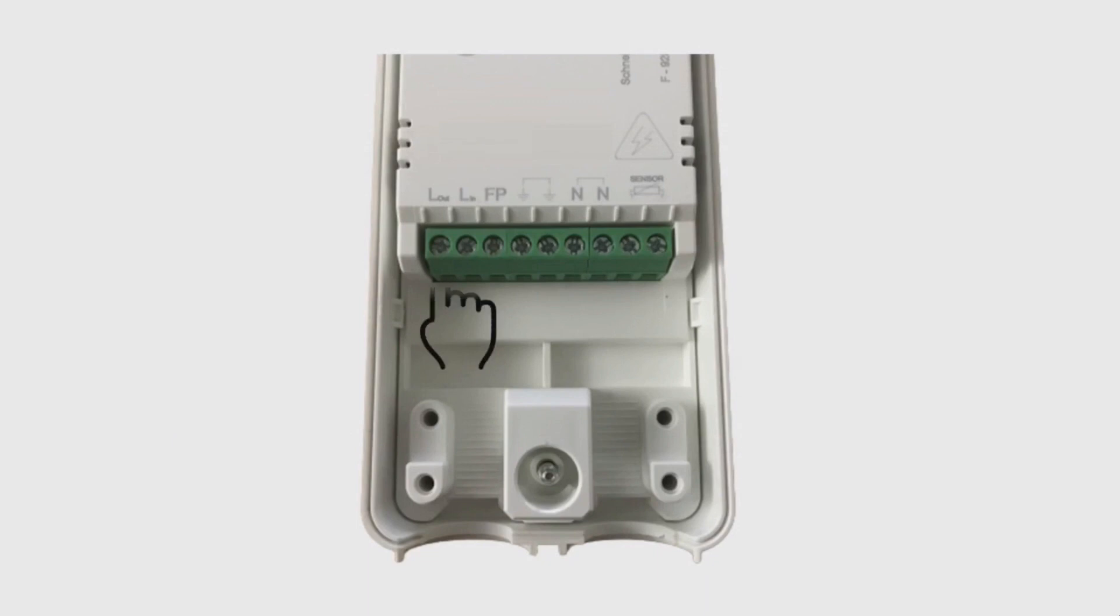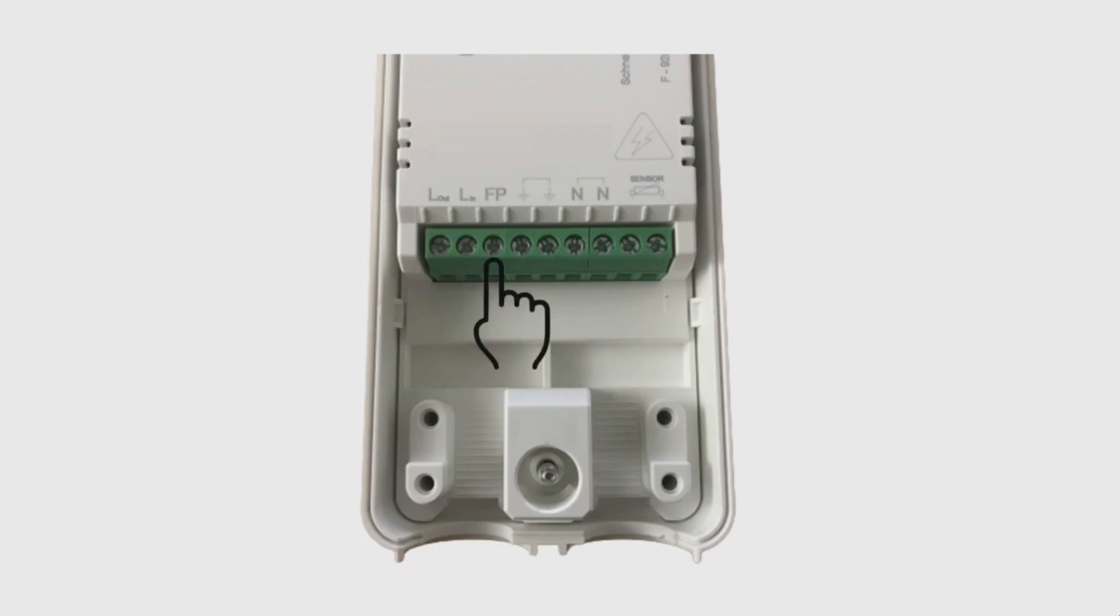Starting on the left, this is our live out which will be the live feed to the load that is being controlled. Here is the live in which will be coming from the supply, most likely a fused spur. Next is a pilot wire connection which is a feature on some electrical heaters found outside of the UK. It isn't supported by Wiser so you'll never connect anything to this terminal.